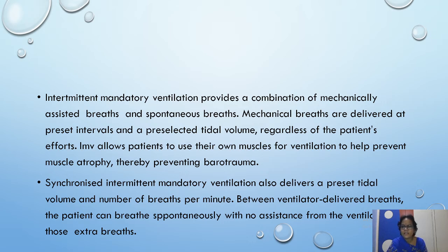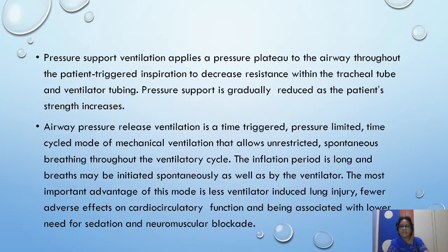Another one is synchronized intermittent mandatory ventilation, which also delivers a preset tidal volume and a number of breaths per minute. Between ventilator-delivered breaths, the patient can breathe spontaneously with no assistance from the ventilator on those extra breaths. When the patient is able to take breaths, the ventilator will not give any breaths or tidal volume. When the patient is not able to, only then does it give the ventilation. This is also an advanced mode of ventilation.